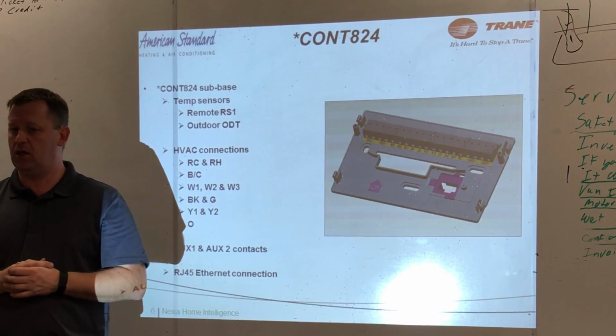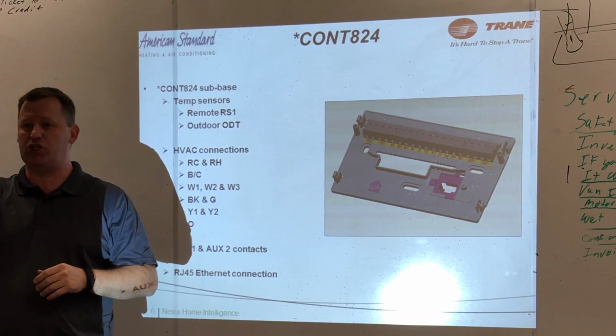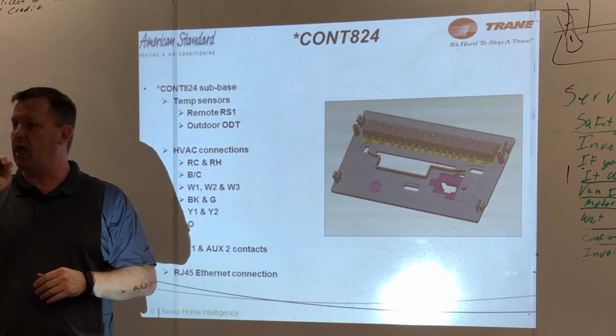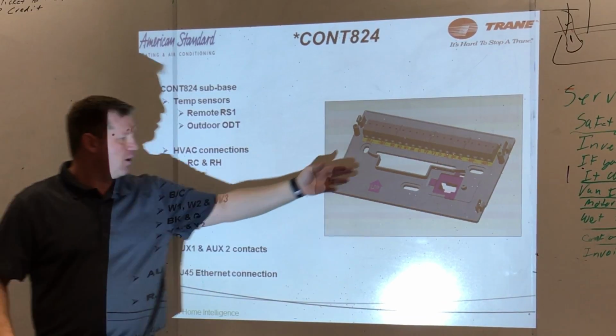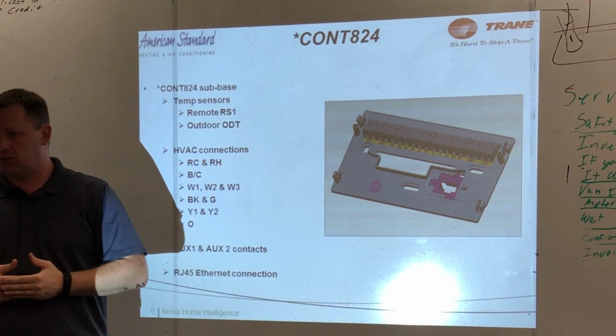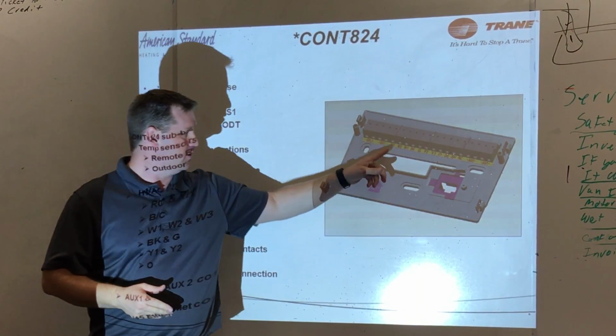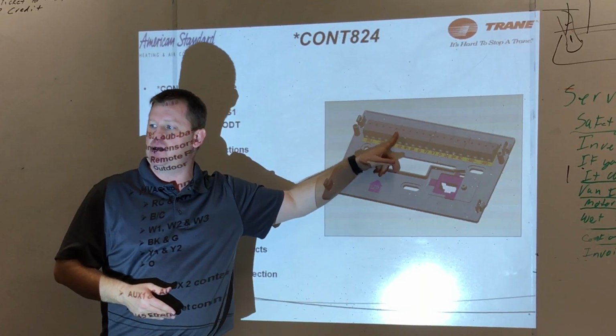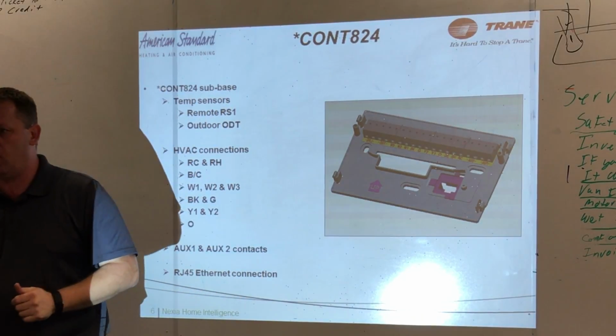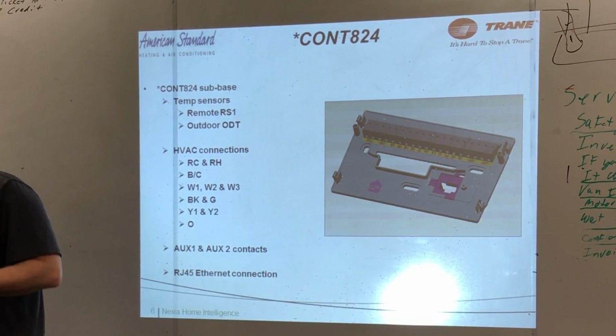I've seen these stats just start flashing like a strobe light. There are some issues with using that outdoor sensor, and it's not a short. It's interference coming off the AC into that DC signal. Once we separate the wires, the problem goes away, so pay attention to that stuff.